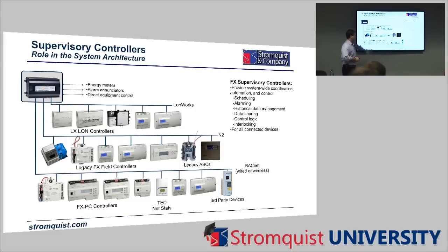All right, so your Jace is responsible for all of this stuff. Scheduling, it's going to write a schedule for all these controllers to follow. Now, we can have several different schedules. We're not set up where we just have our 8 to 5, open and closed type scenario. We can have a schedule that says, here's our holiday schedule. So we're a school. Here's all of our teacher work days. Here's all of the early releases. Here's all the holidays that come about, and we can have schedules that override all those schedules so that your building is only operating when there's people in it.